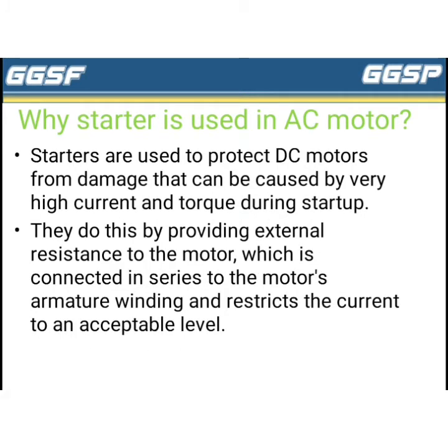Why is a starter used in a DC motor? Starters are used to protect DC motors from damage that can be caused by very high current and torque during startup. They do this by providing external resistance to the motor, which is connected in series to the motor's armature windings and restricts the current to an acceptable level.